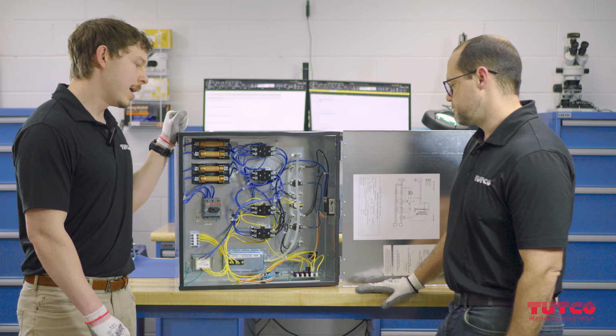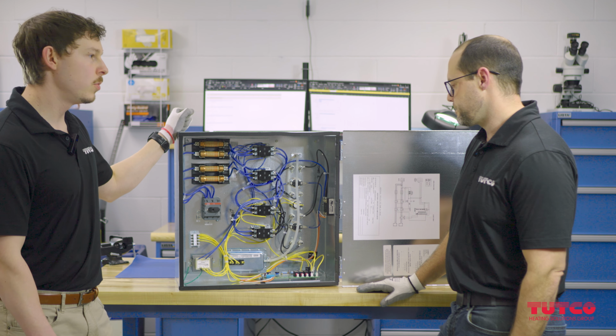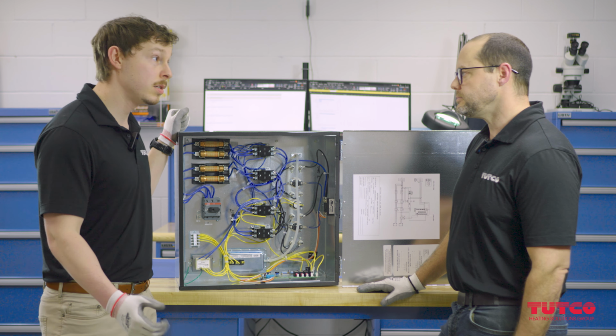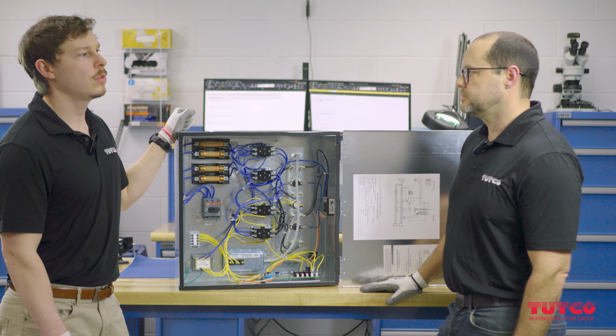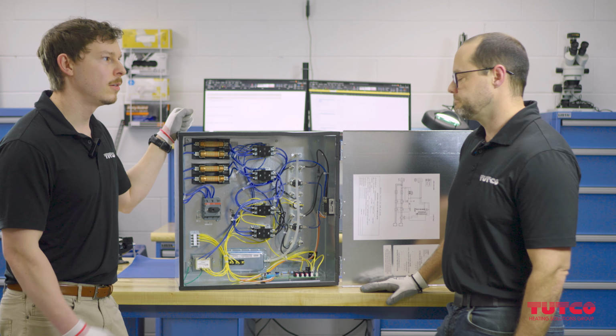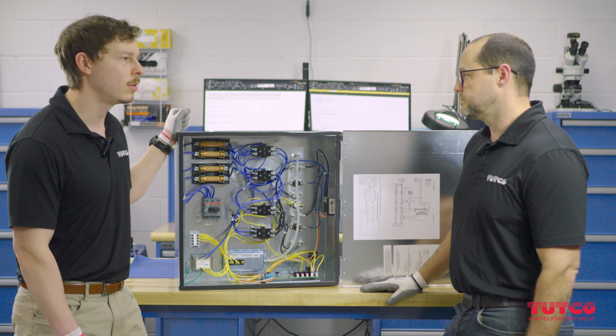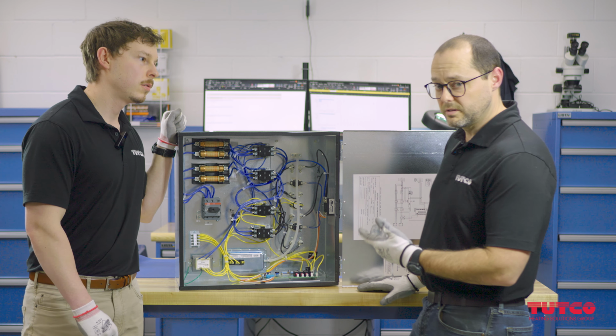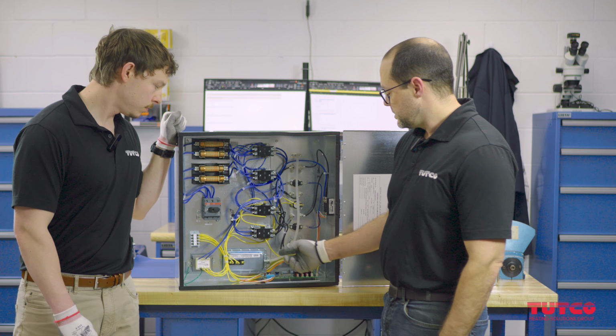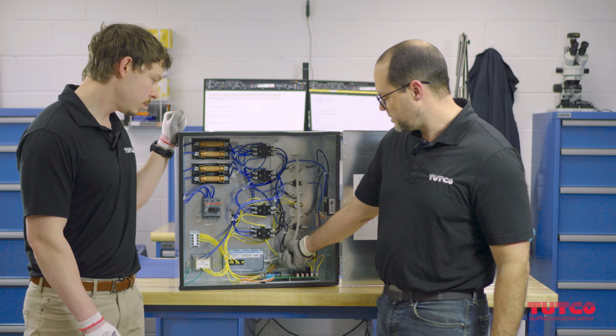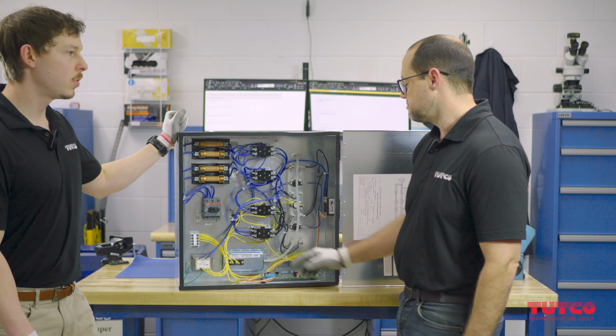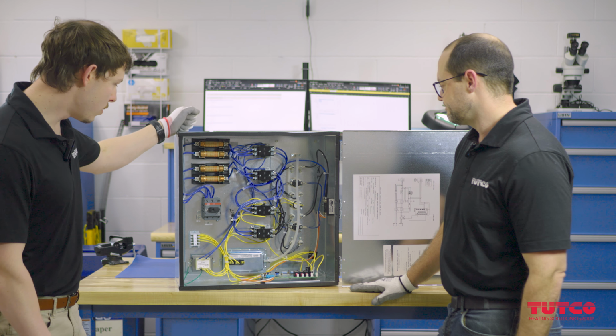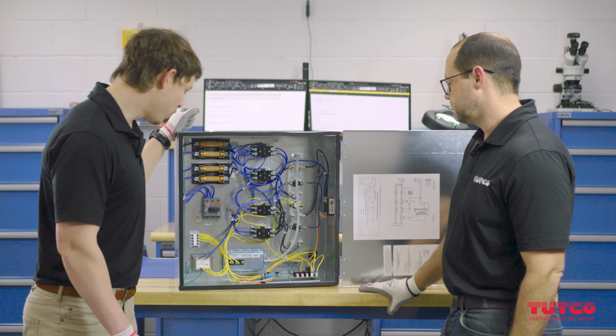Interesting. So I had a situation where we had to move our heater. Fortunately, it was an E-series heater, but we had to move it to the draw-through side of our ducting. So is that going to still apply here? So what you'll need to do if you have a draw-through application is you'll need to move the tube to the other port on the airflow switch. Perfect. Yeah. Very good. So I also heard you mention the transformer.